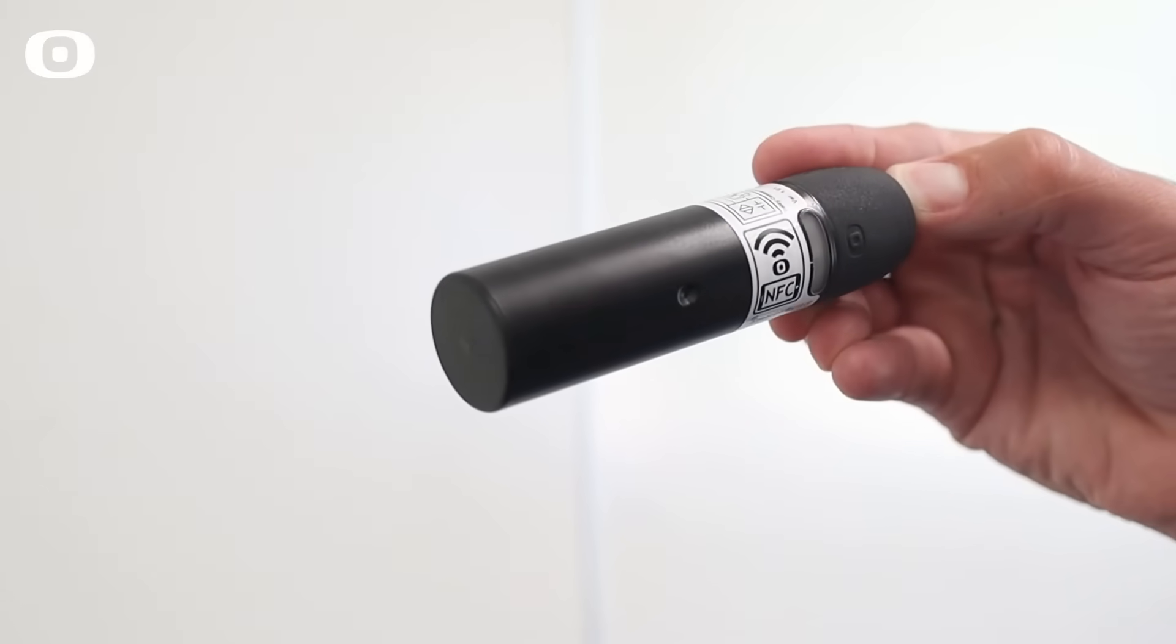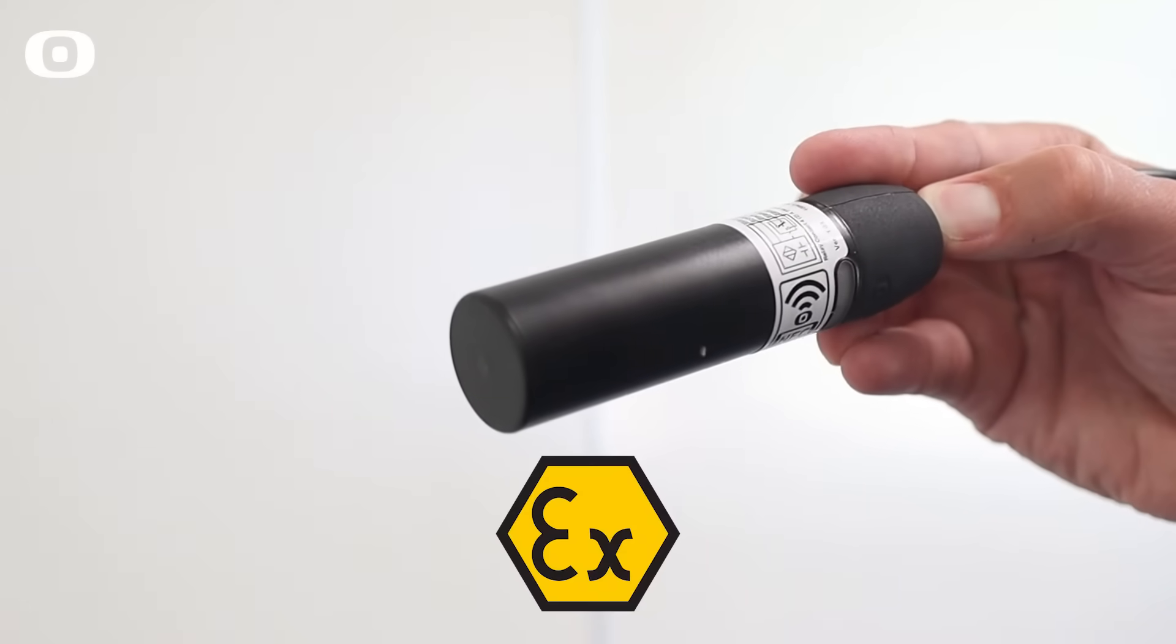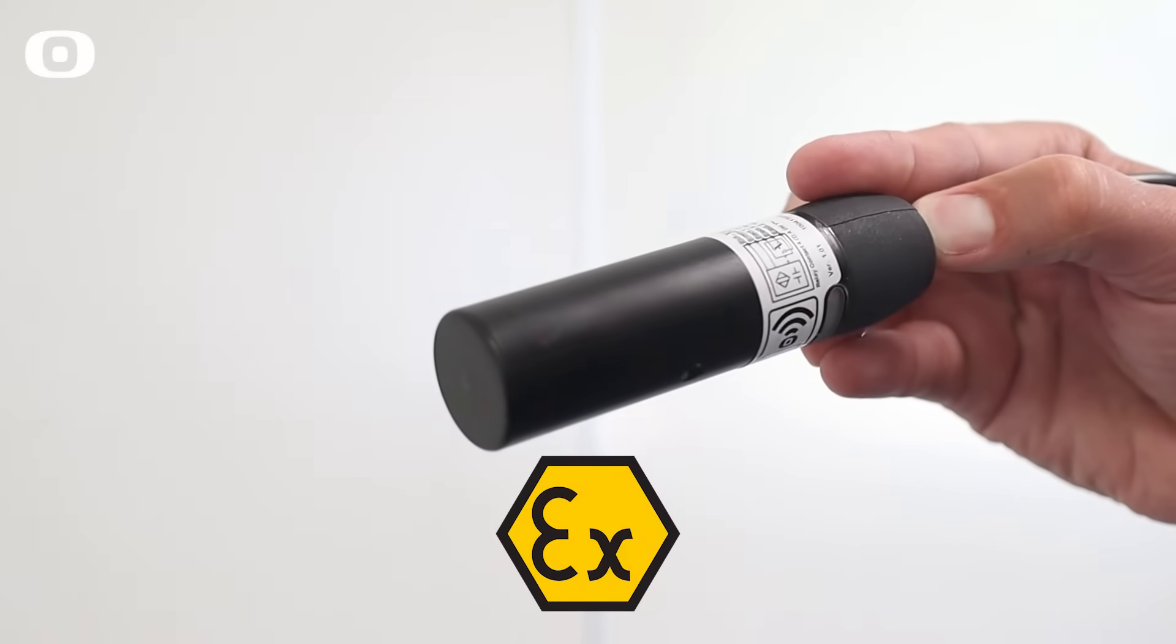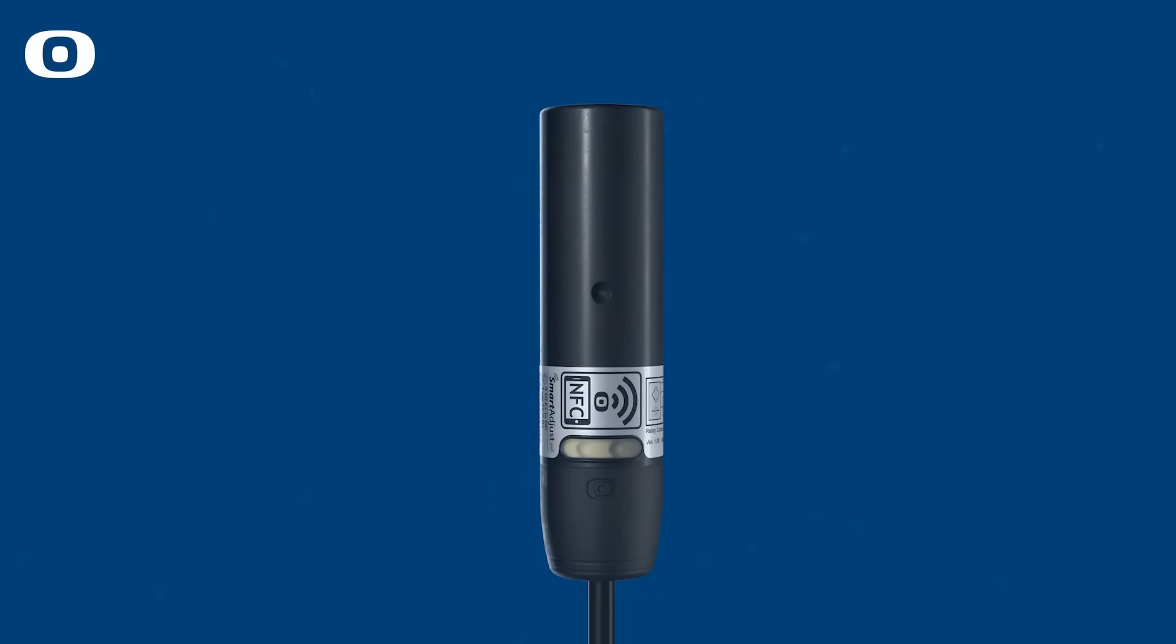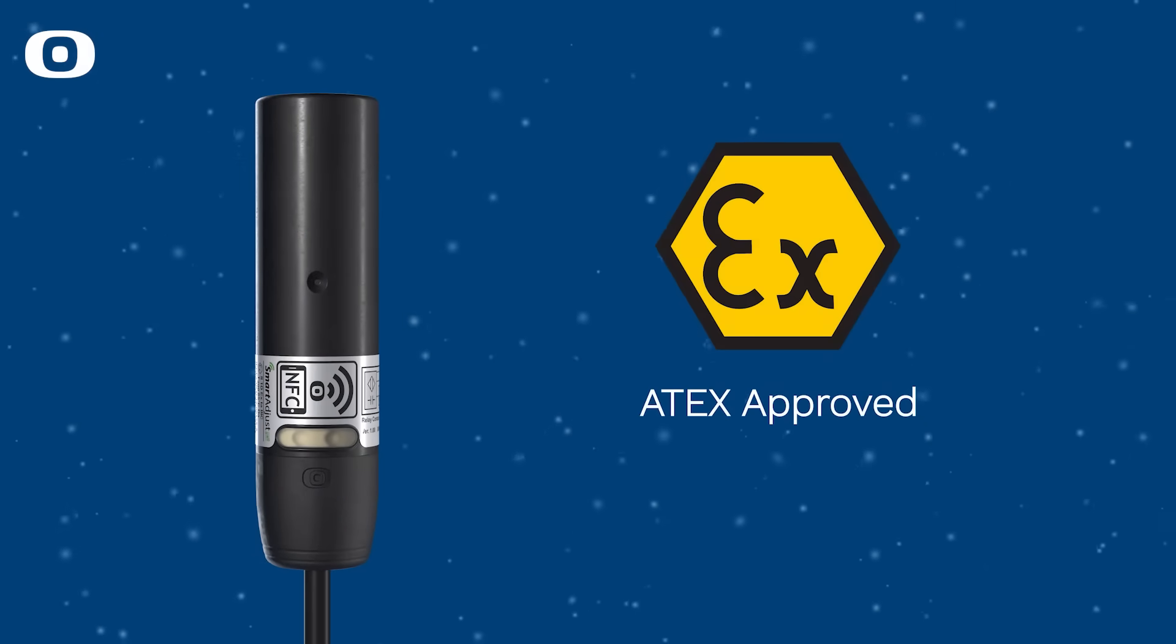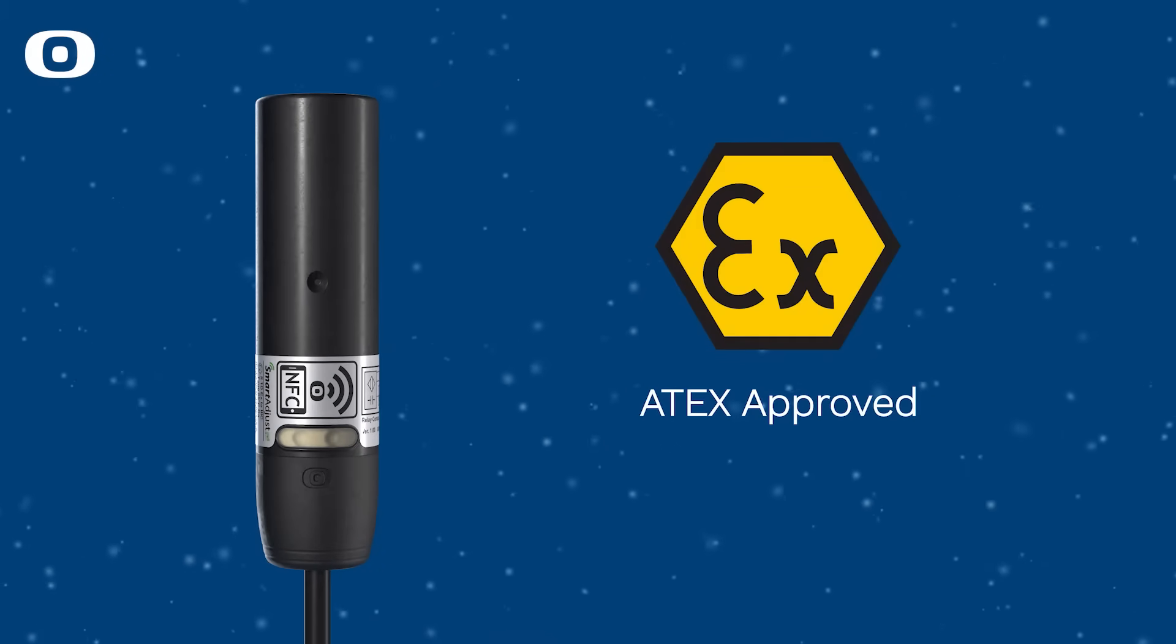IDOL 46 sensor is a 30 millimeter ATEX approved capacitive sensor. The ATEX approval makes the sensor suitable for installations where dust poses an imminent explosion risk classified according to zone 20 and 21.